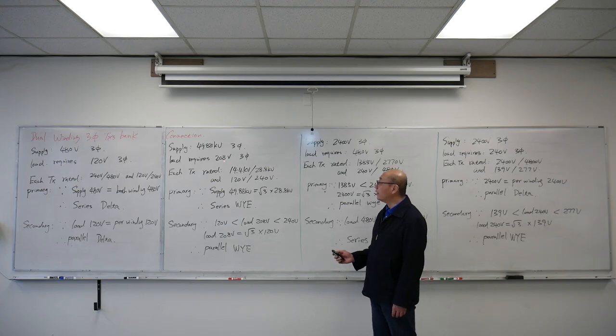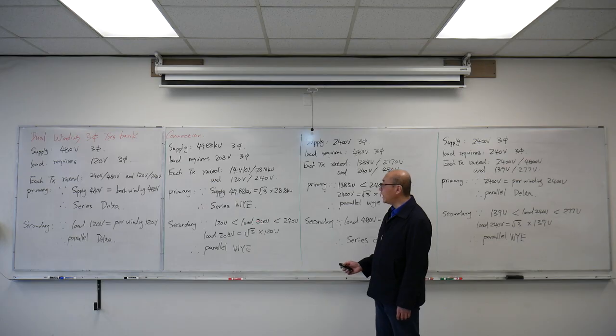Secondary side, 208 volts. 208 volts is not equal to 120, and it's also not equal to 240, so I know it's not going to be delta. Now, this 208 is higher than 120 but lower than 240. So all I have to check is whether 120 times root 3 equals 208. Yes, it equals 208. Now I know the secondary side is connecting parallel Y.